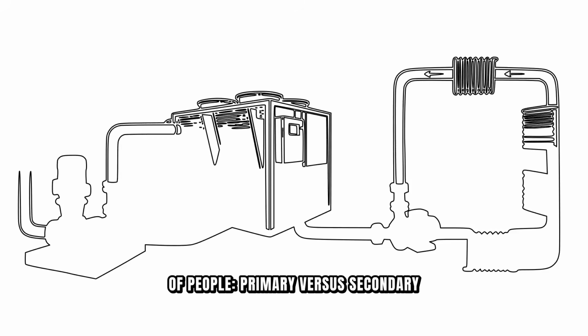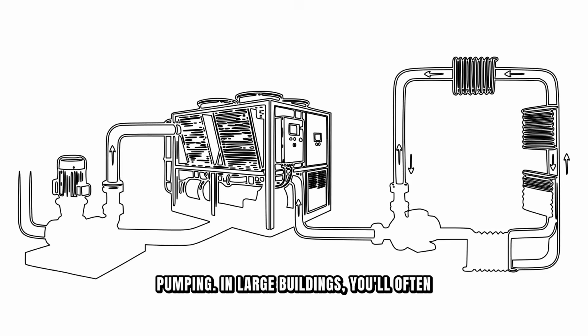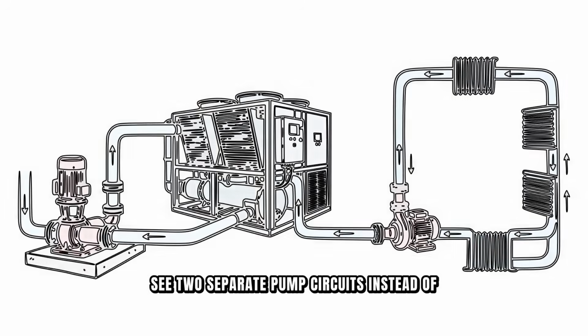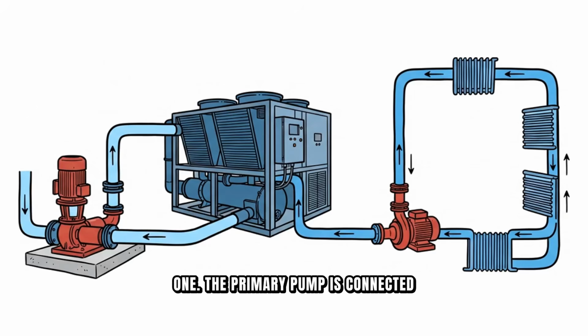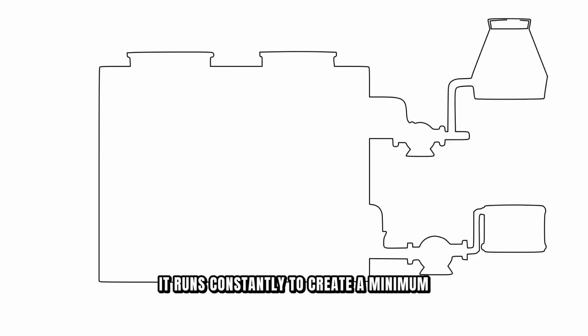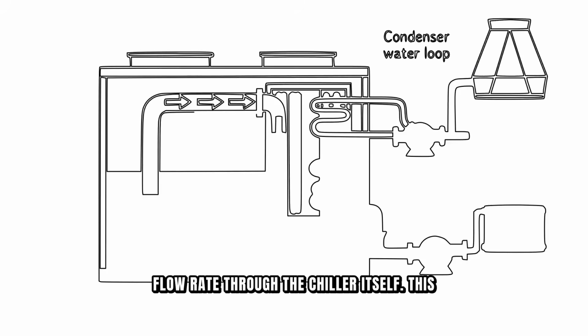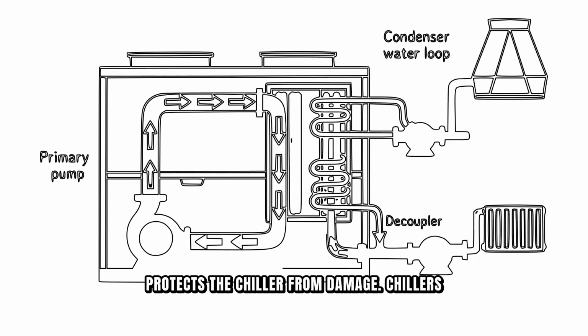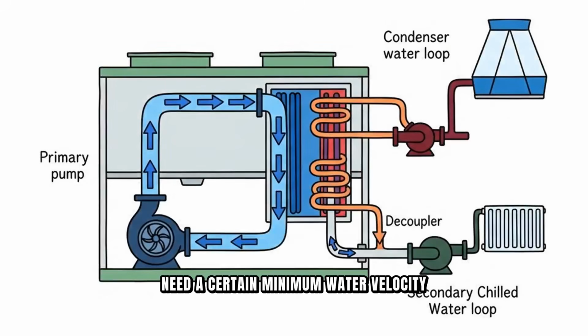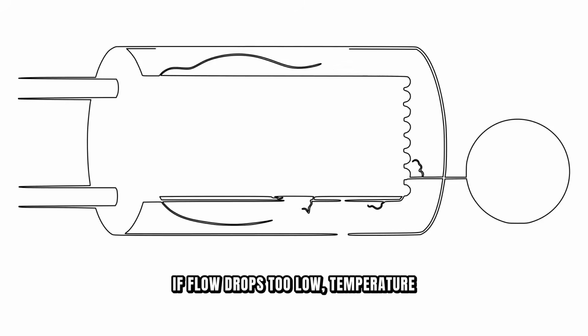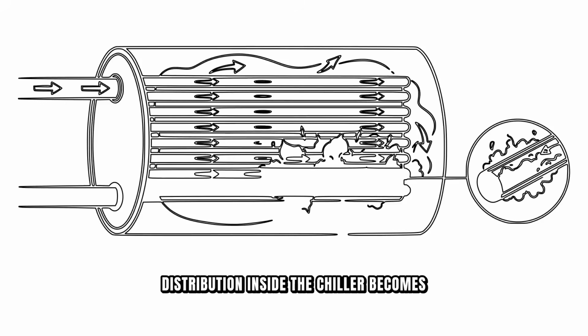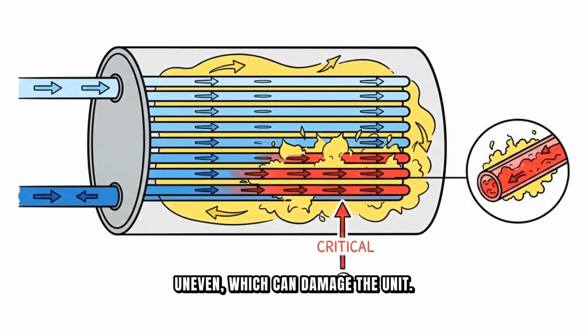Here's a concept that confuses a lot of people: primary versus secondary pumping. In large buildings, you'll often see two separate pump circuits instead of one. The primary pump is connected directly to the chiller or heat source. It runs constantly to create a minimum flow rate through the chiller itself. This protects the chiller from damage. Chillers need a certain minimum water velocity flowing through them at all times. If flow drops too low, temperature distribution inside the chiller becomes uneven, which can damage the unit.